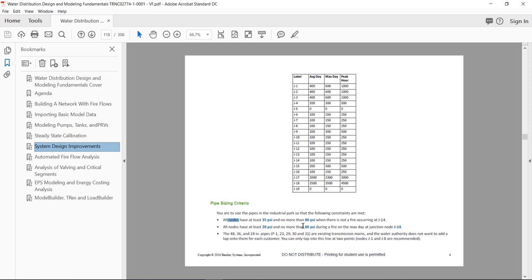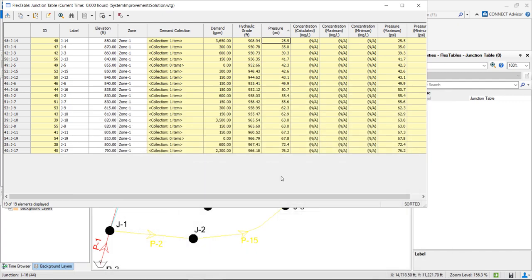The criteria of 80 psi maximum is also achieved because the maximum is 76 psi. This was already met before — if it's met for low demands, of course for the fire flow scenario with higher demands the pressure will decrease more, so it will also meet this condition.